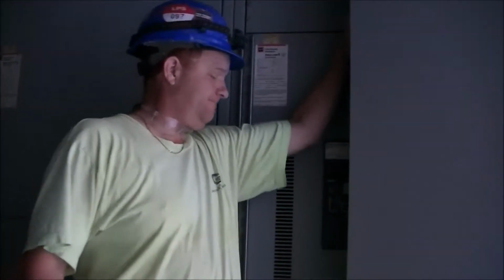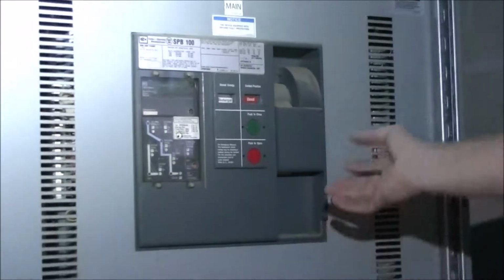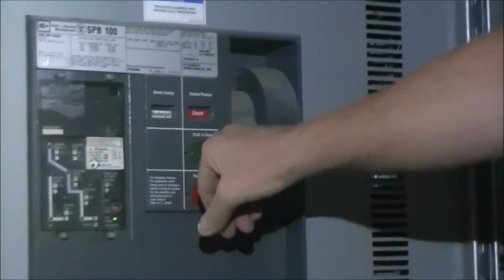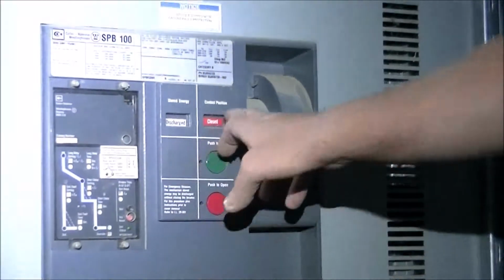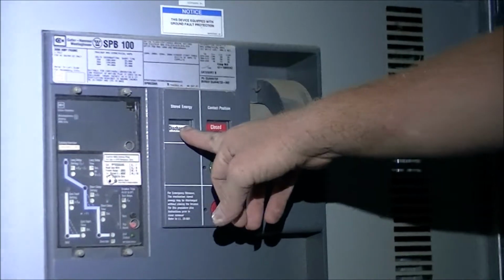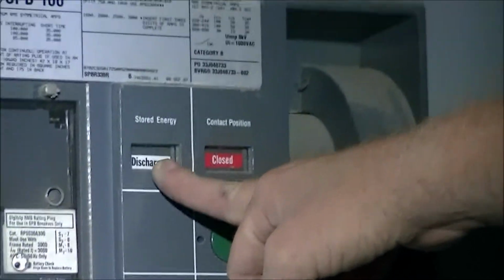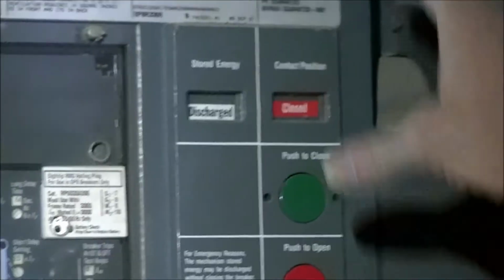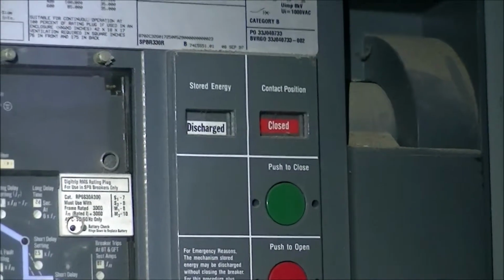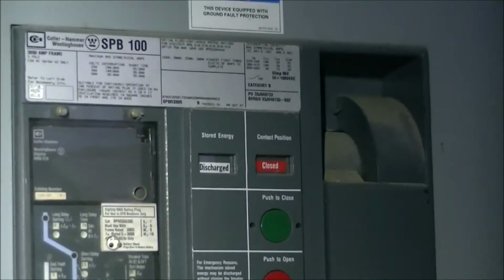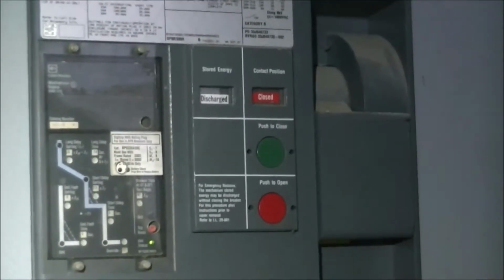This is a little bit of a strange piece of kit that if this ever does go out, then it has to be primed before it will go back in. Pull the handle out, pump it up and down, push the green button, it goes in. It'll always be sitting on closed and stored energy is discharged, but it's not storing anything. Okay? So if that ever goes out, it's probably not something that you want to do yourself. No. It's probably a Tommy thing, getting involved, because it has to be primed and then put back on.